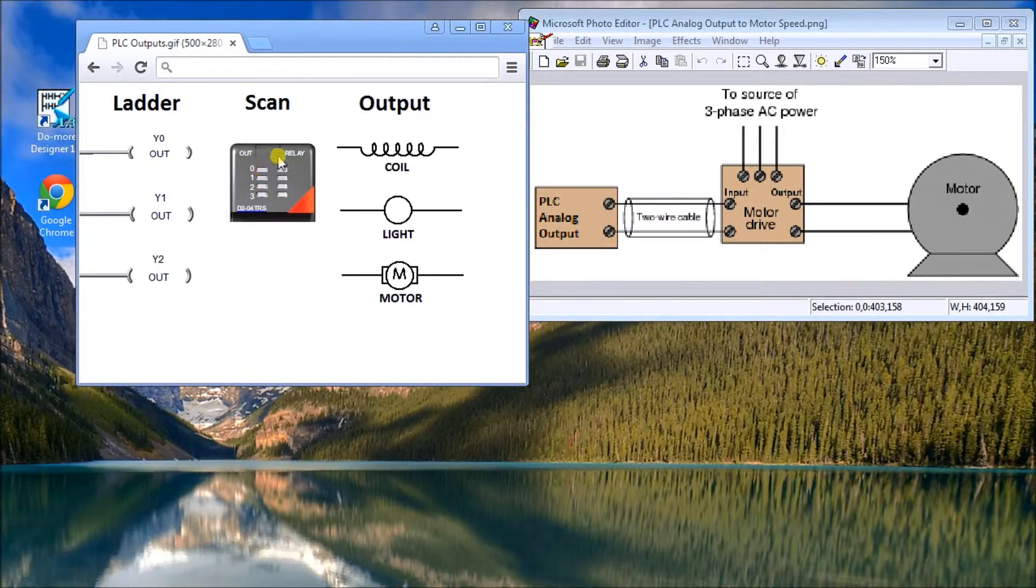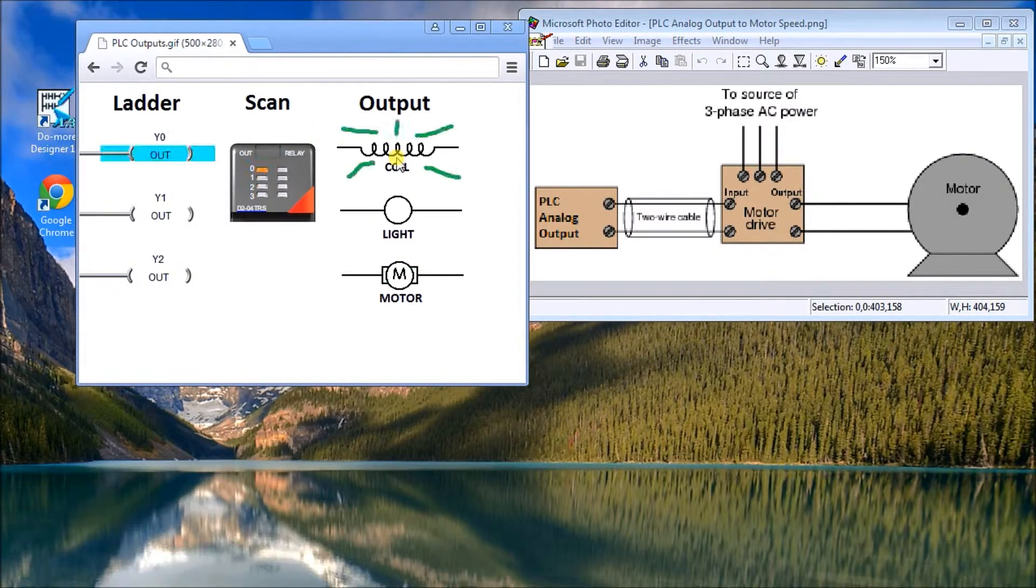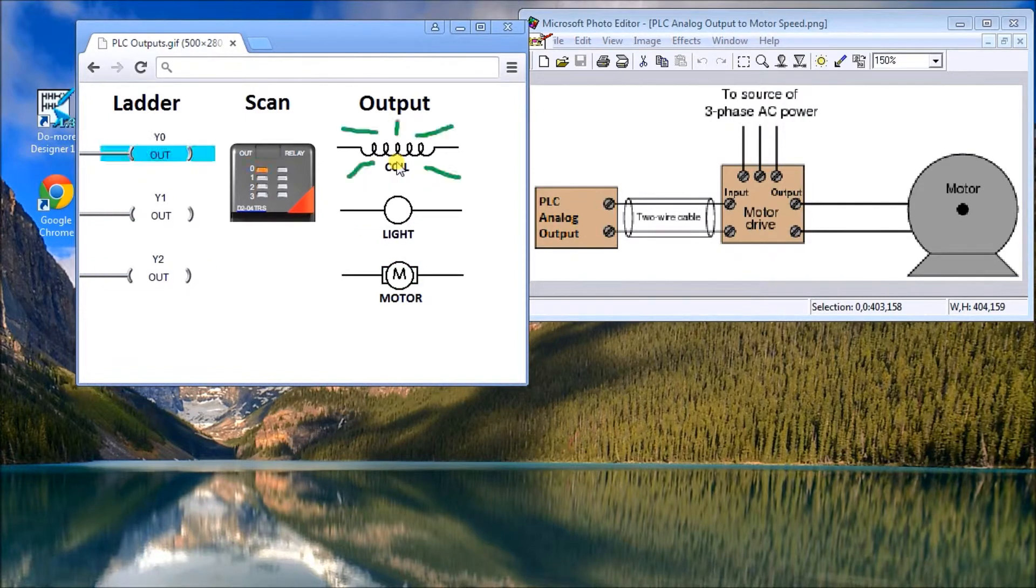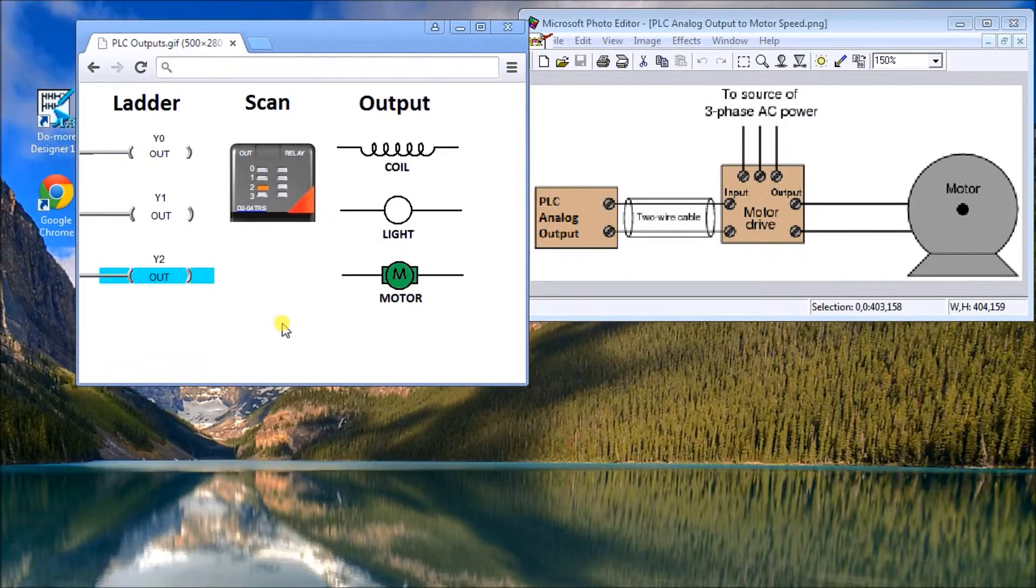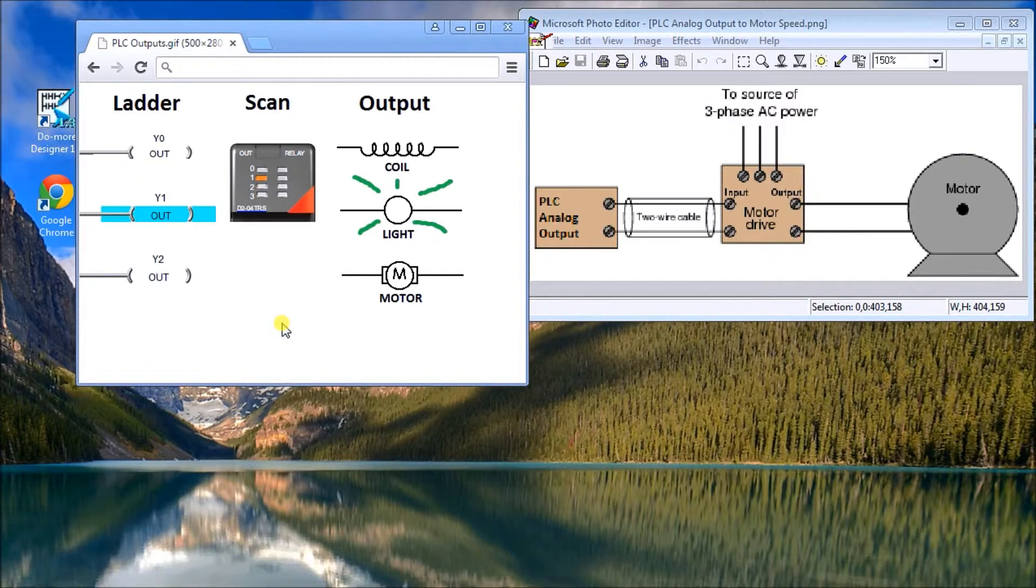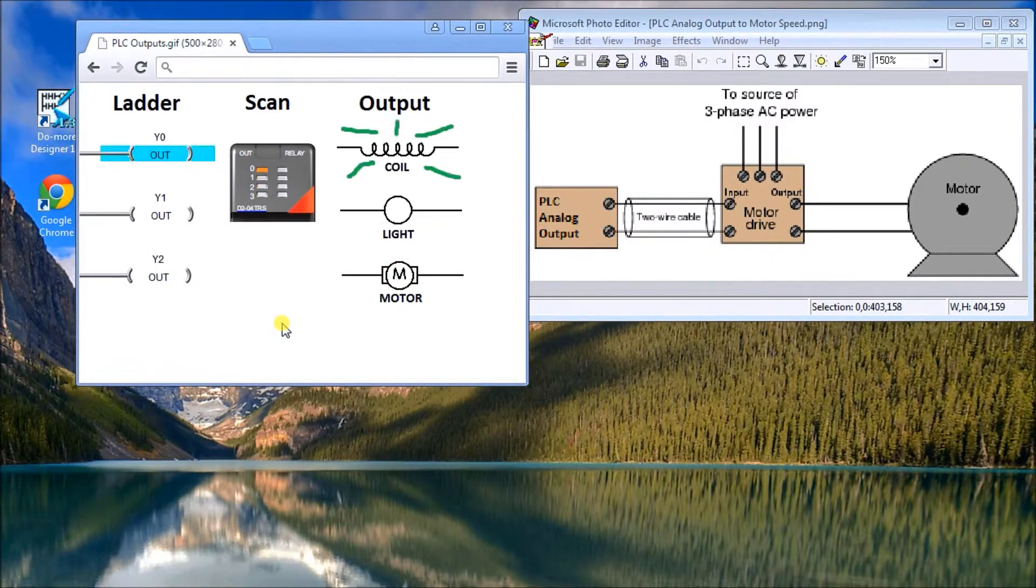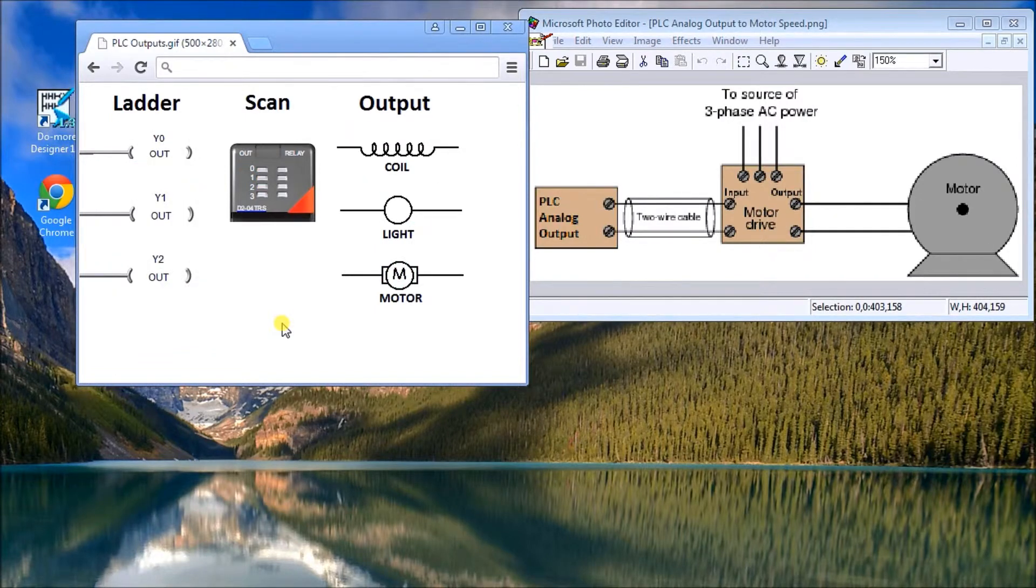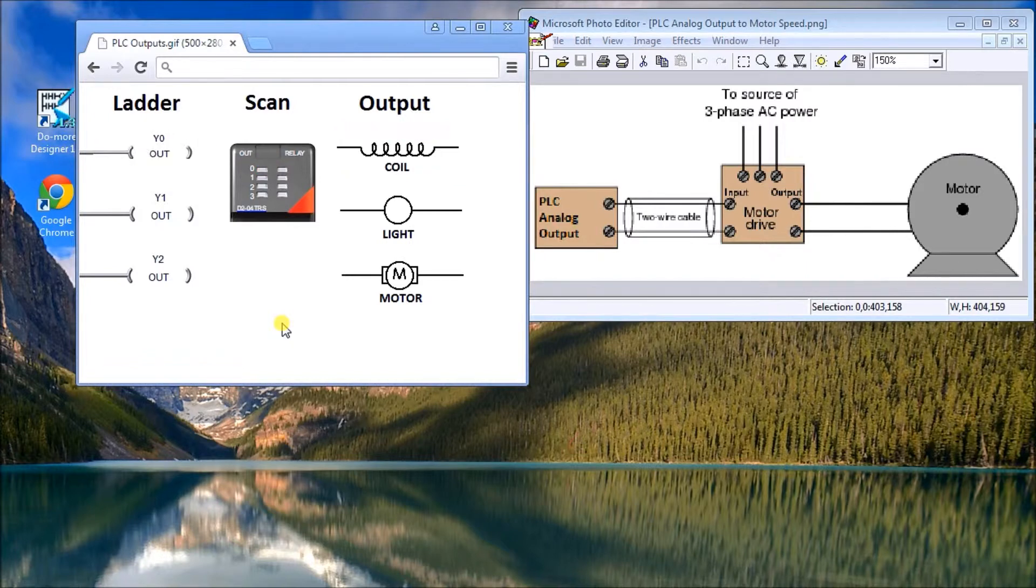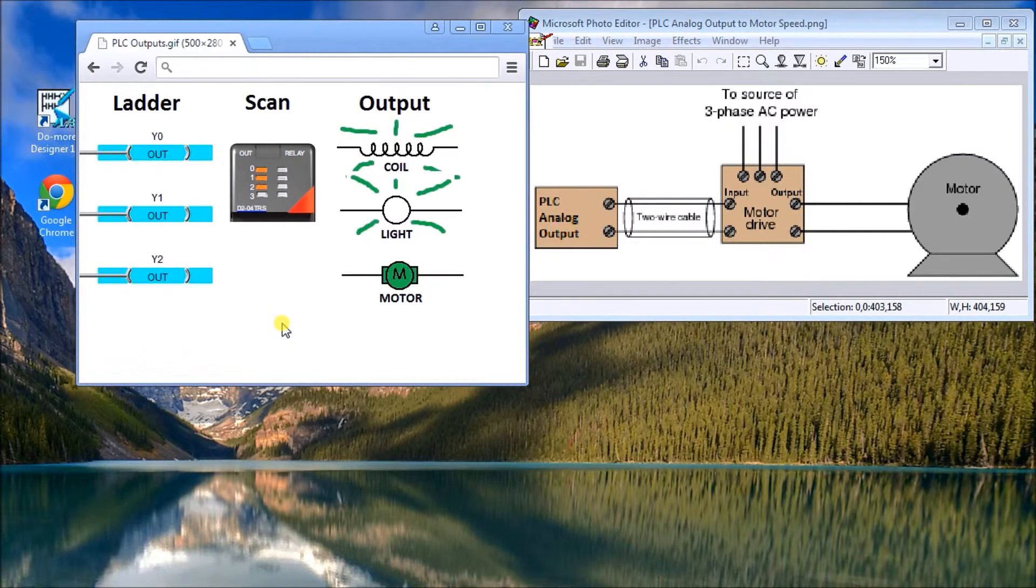This typically takes about one millisecond, so a thousand times a second this happens. It's important to know that you're both setting it and resetting it within that time frame. The fastest pulse train we can get, which means a series of pulses, is going to be 500 pulses a second. You need the pulse on time and the pulse off for a one millisecond scan.